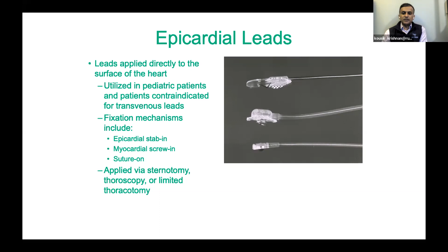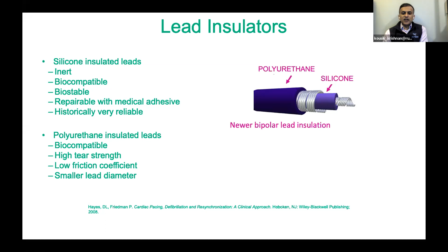The different types of insulation that are used can also differ from manufacturer to manufacturer. They can be silicone, they can be polyurethane, or they can even be some blend of the two. And they have different biochemical and material science properties that make them advantageous: their strength, their ability to be extracted, their resistance to damage, to solute and electrolytes. These are all factors that each of the different manufacturers will promote as advantages to the insulation material for their product. The reality is all of these insulation materials eventually tend to fail, and when they fail, they can lead to electrical abnormalities in the leads.